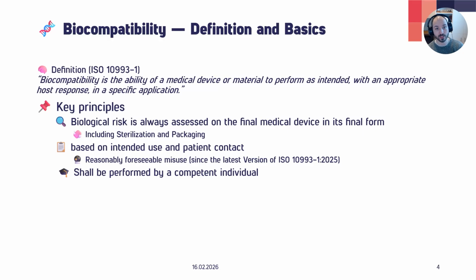And in the newest version of the ISO 10993-1 in 2025, it got an update. Now we also have to take into account reasonably foreseeable misuse. For example, if you have a breathing circuit that's only dedicated as a breathing circuit, you might also foreseeably see that this could be misused as an anesthesia circuit, and you'll have to be planning for that. Or you can say, okay, this is for an adult, and then you could also reasonably foresee that this is used in children or for children. And therefore, you'll have to take into account those cases as well.